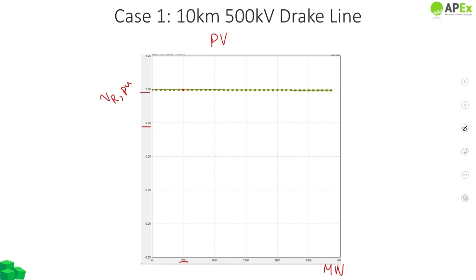Let's try to interpret this graph. For 700 megawatts of power transmitted through the transmission line, the voltage at the receiving end is 1.0, meaning the receiving end voltage has remained within the tolerance band and is the same as the sending end voltage. Now, at 2800 megawatts, the receiving end voltage has fallen slightly to about 0.98 per unit—still pretty close to 1.0 per unit, which is the nominal voltage here.